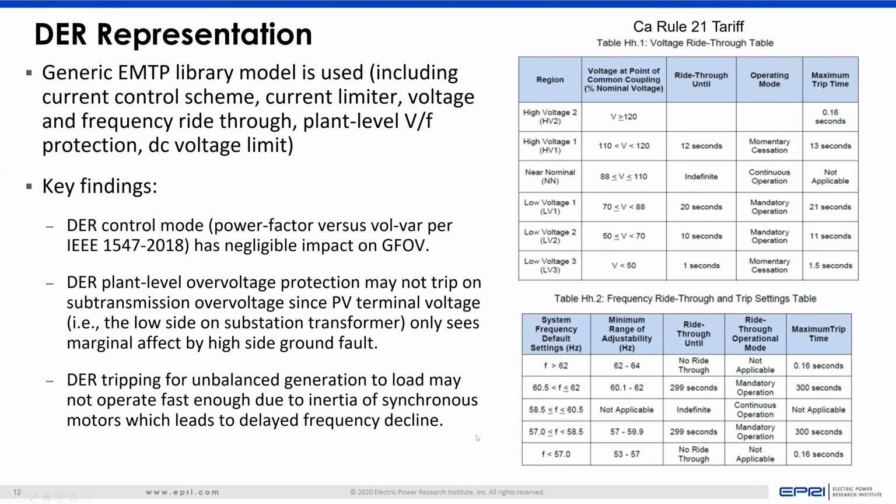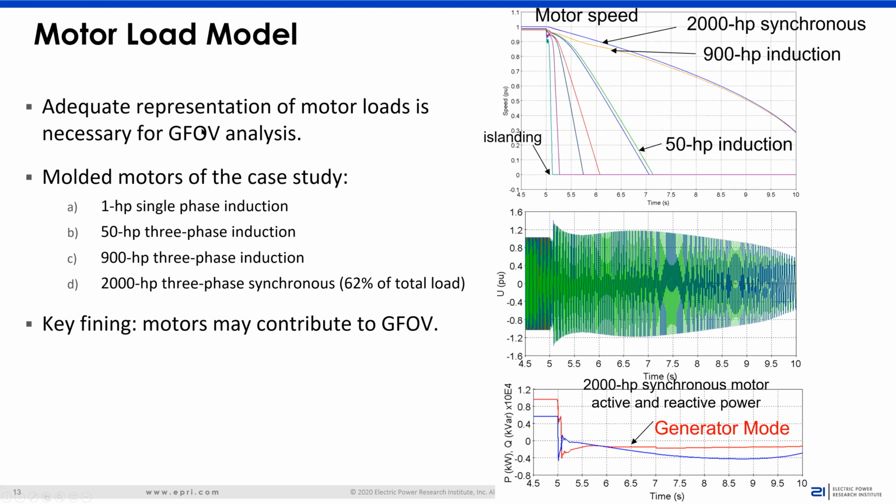And so essentially the conclusion was that we cannot rely on the onboard protection to trip during the ground fault. And motor loads, it's necessary to adequately represent them.